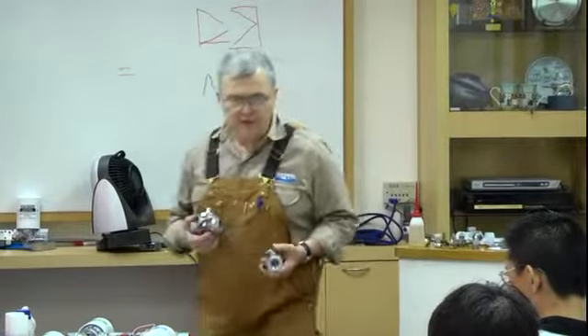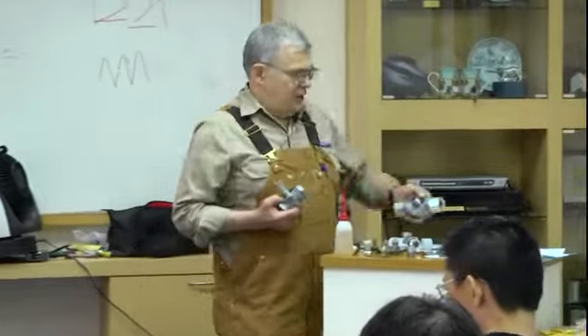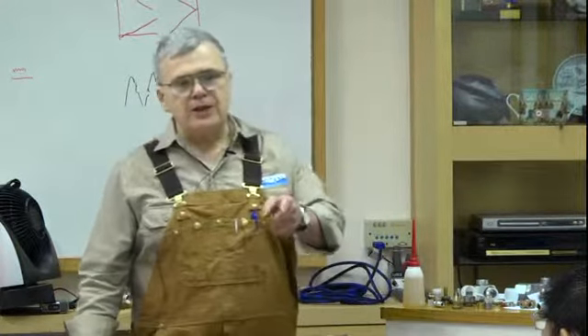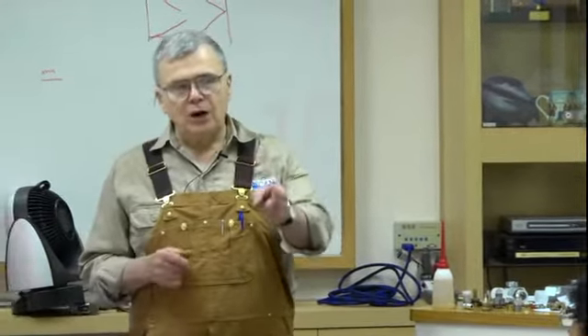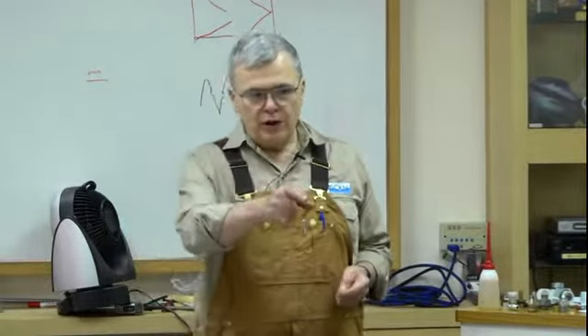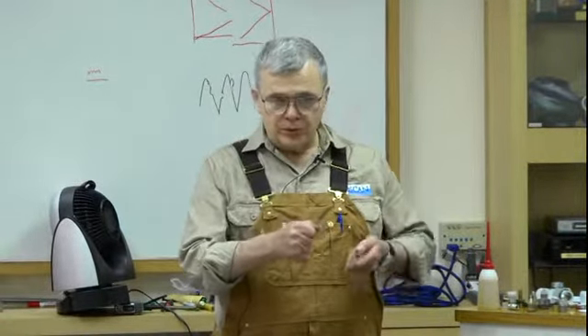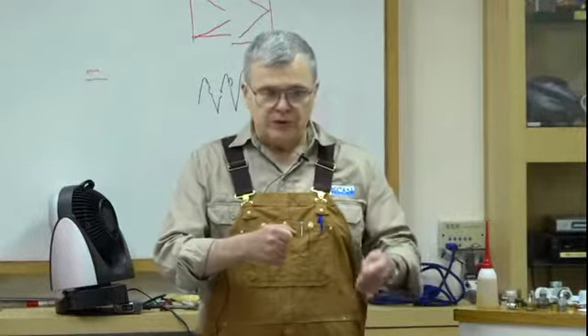That hex fitting, that flow straightener, is Loctited in place with the strongest Loctite known to man. If you rotate that fitting within the body of the sensor and crack the Loctite, you destroy the sensor. So whenever you put a fitting into that sensor, you always use 2 wrenches. One of the wrenches acts as a counter torque, and then the other wrench screws the fitting in.